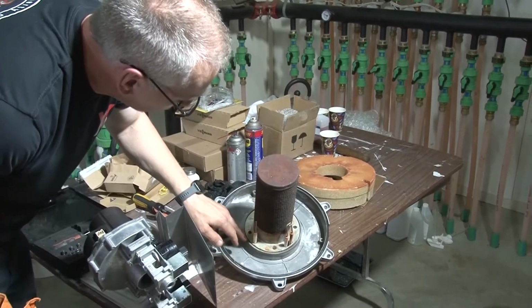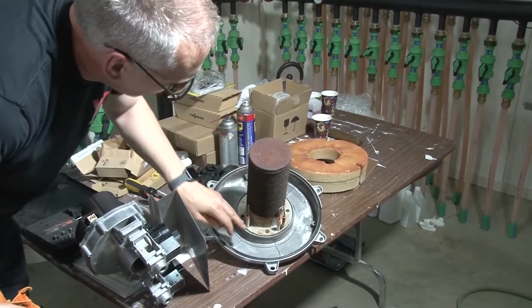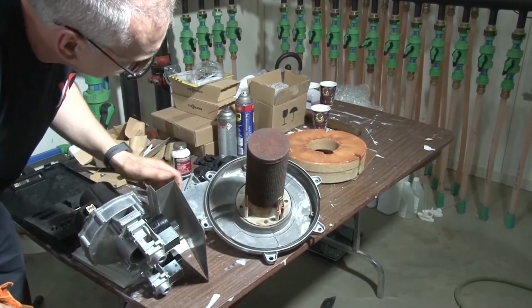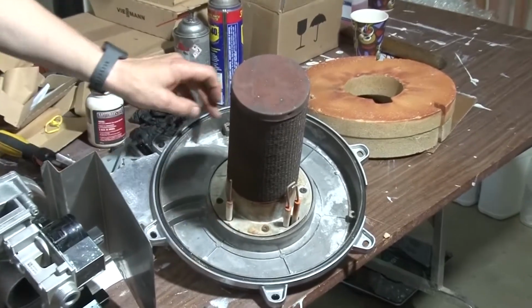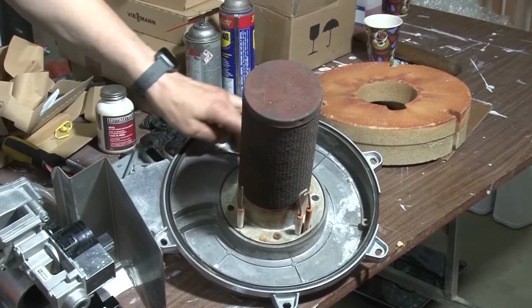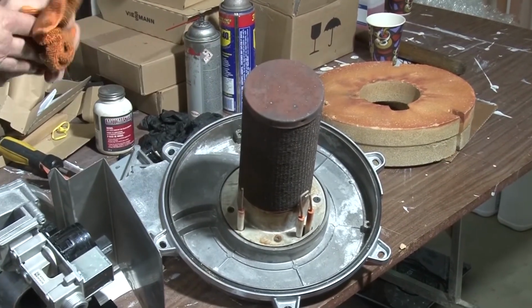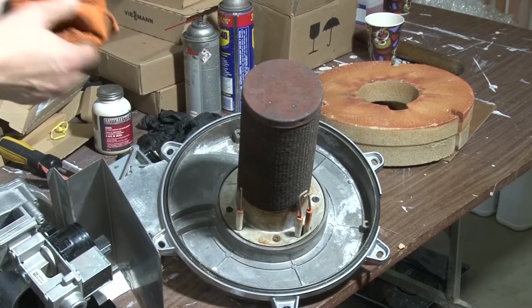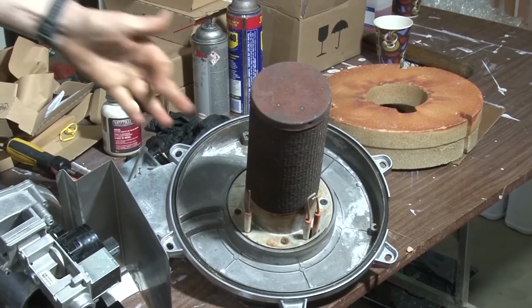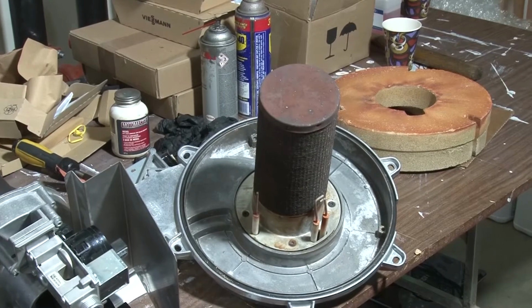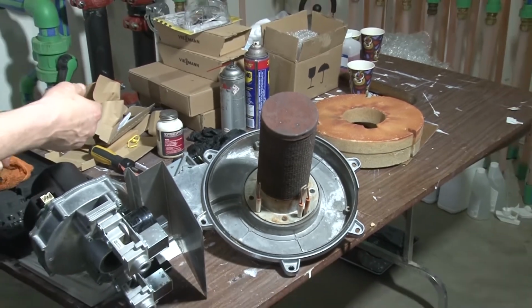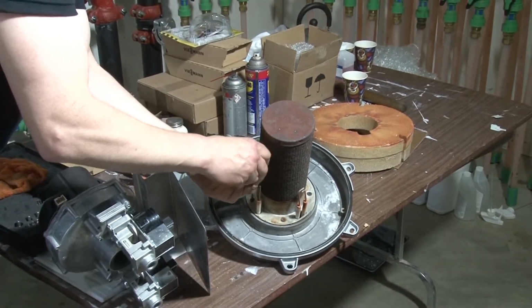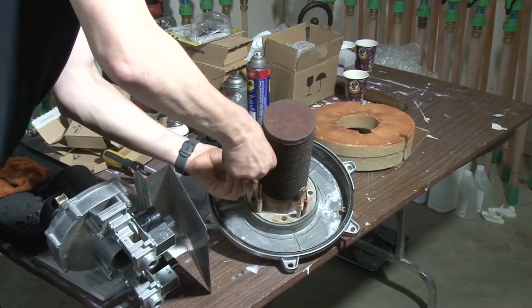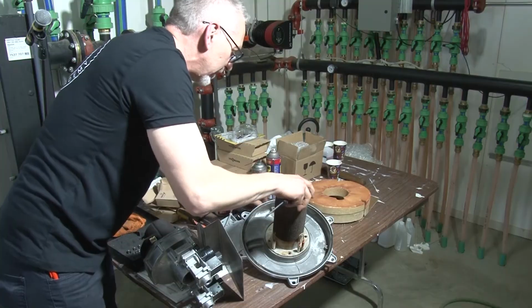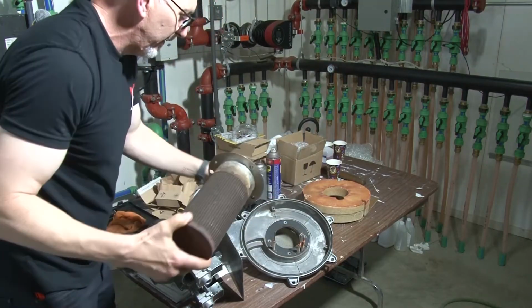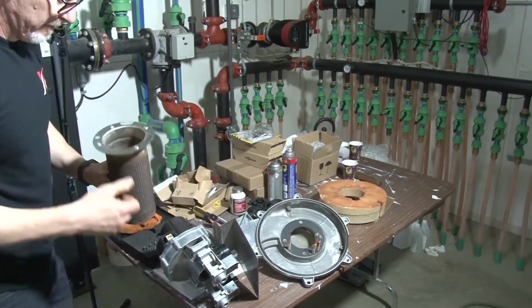This burner gasket is sealed in between the flange and the burner tube itself. If I see any evidence of flue gas escaping in here, any areas here, that could give me an idea that there might be an issue with combustion as a result of a cracked gasket or something like that. If I'm going to clean it, the idea is to pull this burner tube right out. All right, so now we can take that out. And there's your burner gasket.